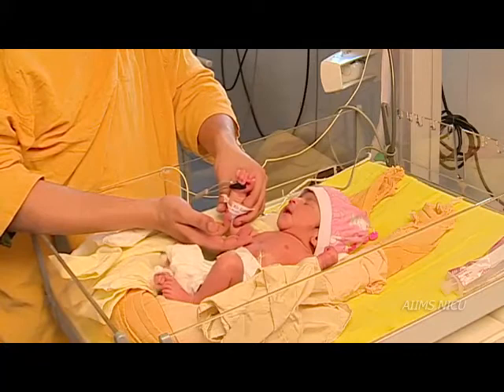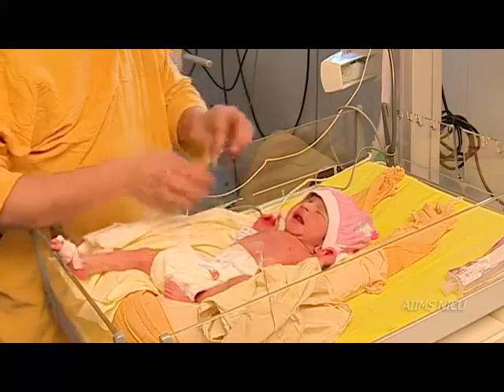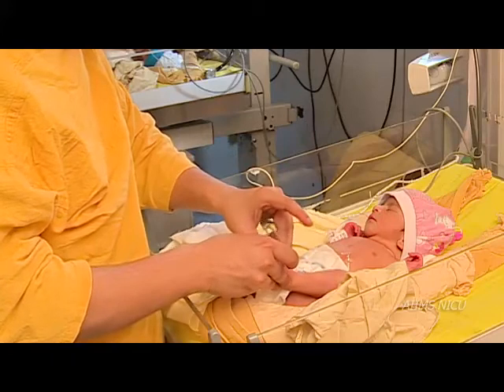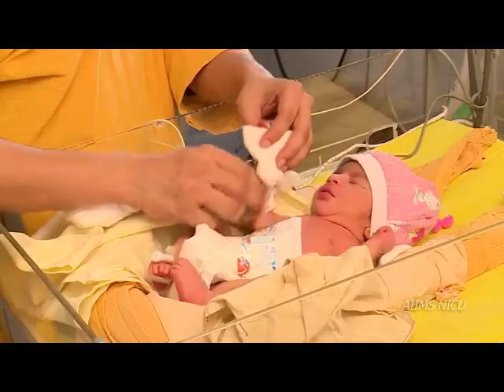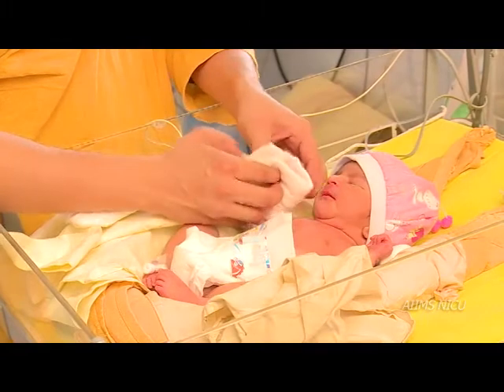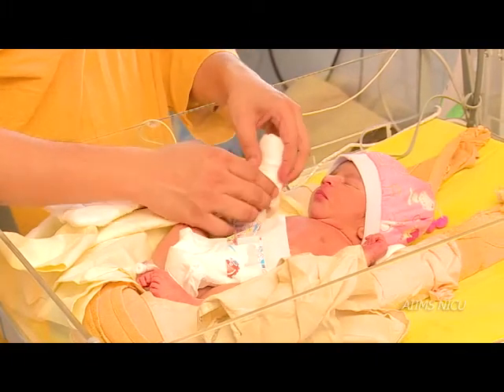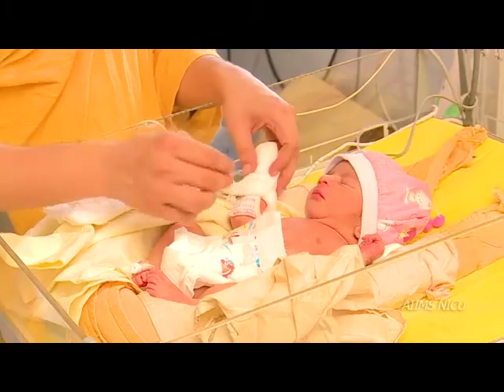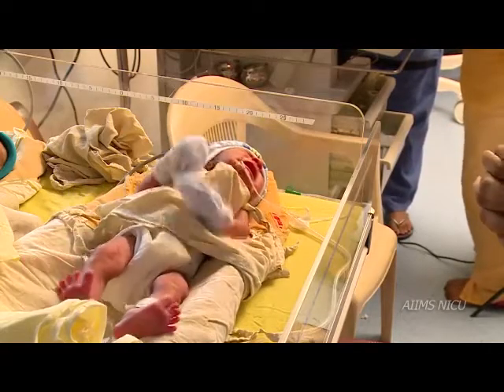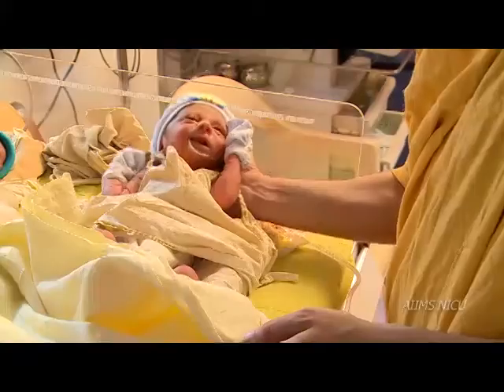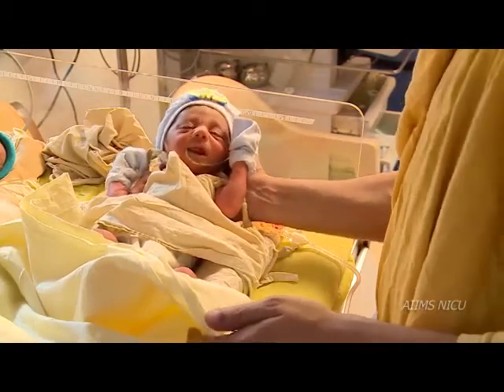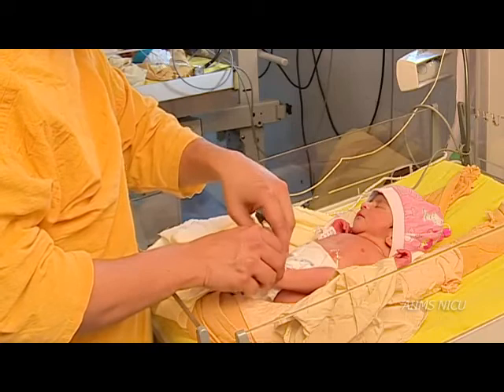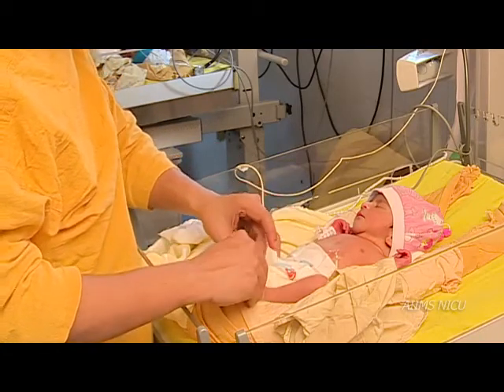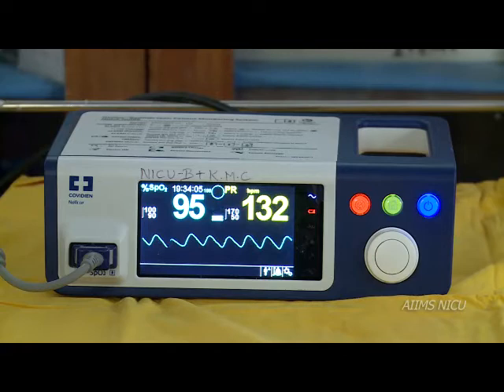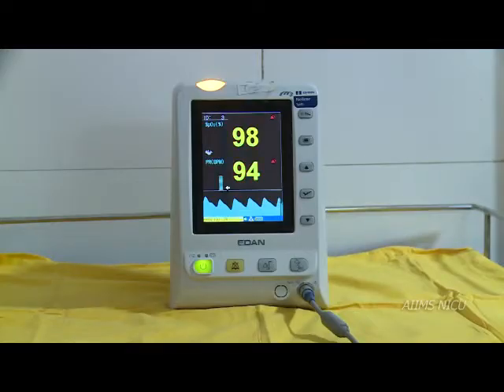For cold extremities, one should remove the probe and reapply in a different site. Wait for the baby to get warm. For excessive ambient light, one should switch off the light source if possible or cover the extremity with a cloth. For excessive movement of a limb, the baby should be comforted and the site of the probe can be changed. Low perfusion requires appropriate treatment measures to improve perfusion. Newer versions of pulse oximeters have built-in algorithms to minimize disturbances due to these factors.